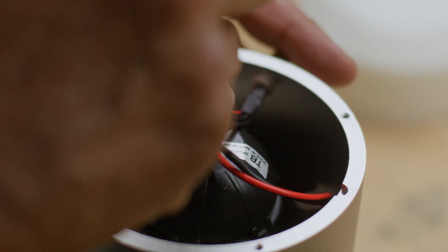We're now on our third generation audio system, which I personally believe we've perfected. We've switched to an actively shielded neodymium speaker. This provides high fidelity sound and high and low frequency response that sounds better, but more importantly does a better job of masking the background noise produced by the MRI.